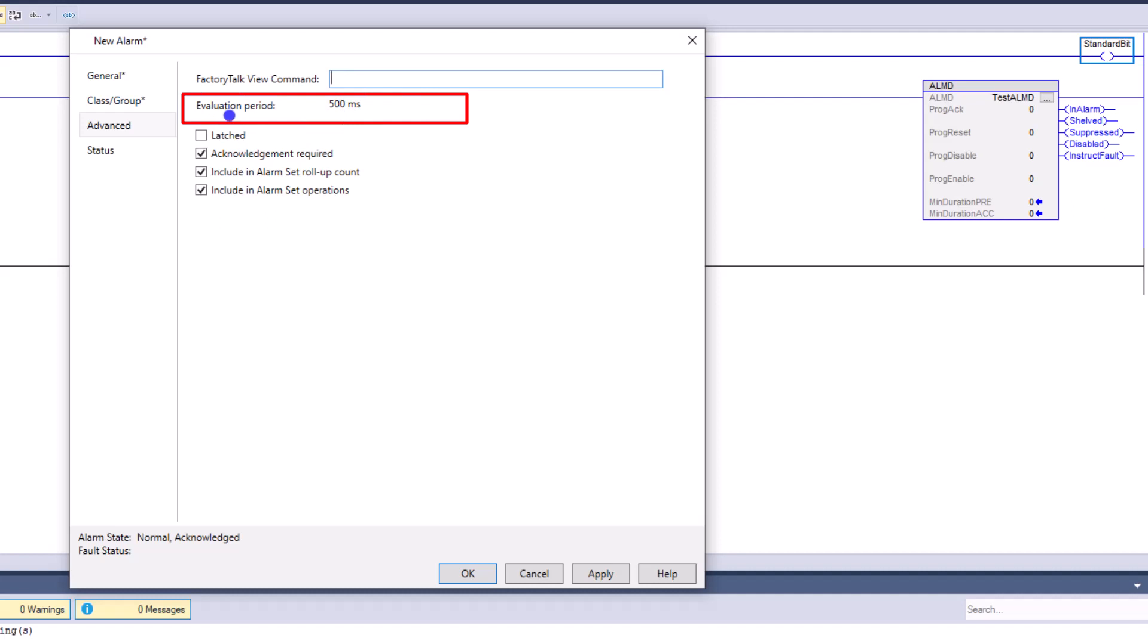The one thing that I do want to draw your attention to is the evaluation period. The evaluation period is basically half a second. So that's 500 milliseconds. With that said, that means no matter when this bit is triggered, when this alarm is triggered, it is not going to issue that command to the actual HMI or to your monitoring system until it's been evaluated in that 500 milliseconds. Now, again, that's based upon the timing of the processor and stuff like that. So there is no real timestamp on that. Besides that, when it gets put on, when it gets evaluated, now that evaluation time, again, is 500 milliseconds. And currently it's not changeable.